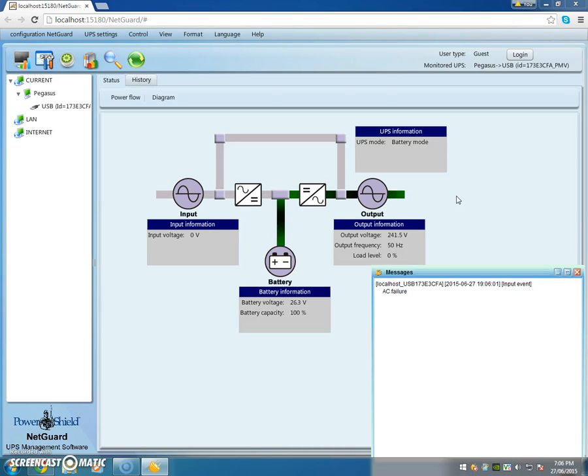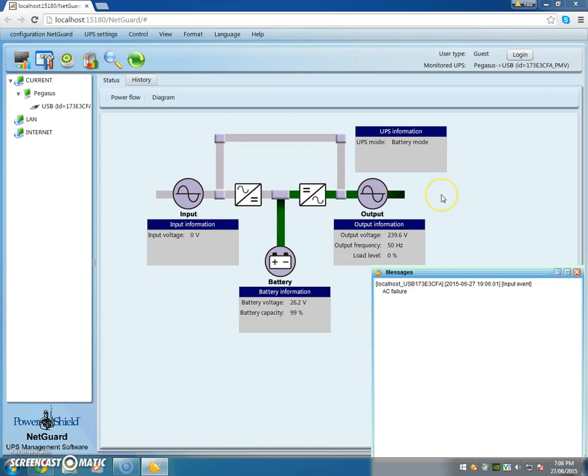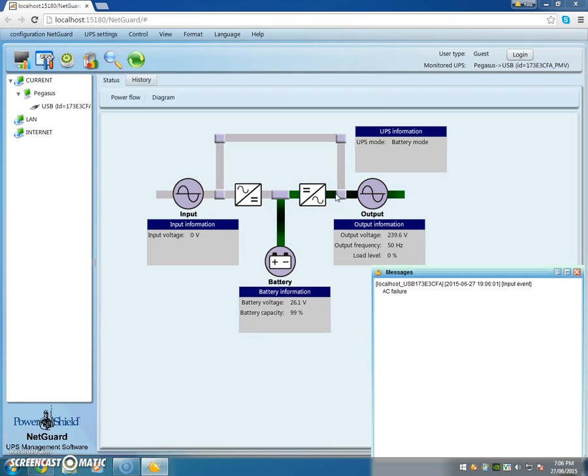Okay, so you can see it goes into AC failure and the input voltage goes to zero. This line path here is non-existent and power is being fed directly off the battery through the inverter, producing a simulated sine wave output to the load.